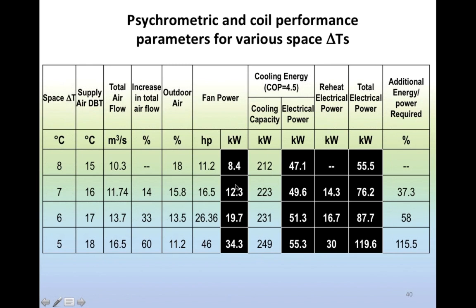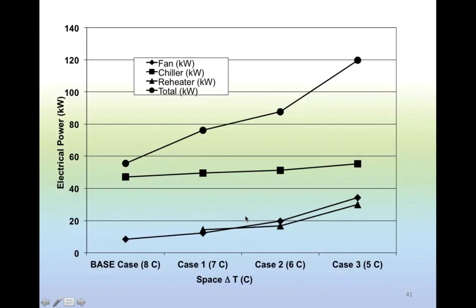And notice the other consequence. The smaller the delta T, we also increase the fan power because you now need to move a lot more air. So again, from an optimization consideration for the cooling coil, if we work with a larger space delta T, it's always a good idea. Sometimes we encounter situations, in consulting practice discussions, where we find there's a tendency to have a warmer supply air temperature. The problem is humidity needs to be handled, and in doing so, it could actually incur a higher energy penalty. This is just another way of looking at the same issues.